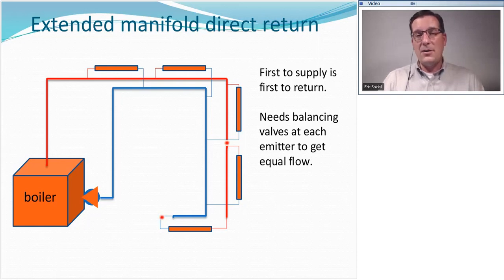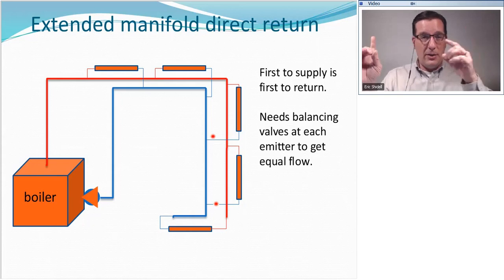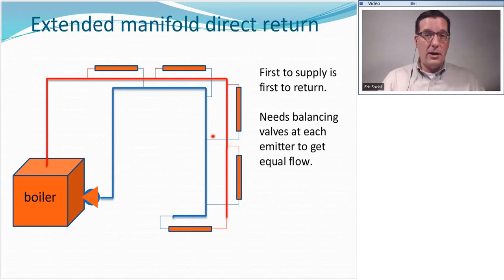But in order to make this work, we have to add the expense of putting balancing valves in each one of these branch lines to equal the flow through the whole system. And that will often be done or not done. Sometimes they're eliminated as a source of value engineering, and that leads to its own set of problems. And then you get another reason to stick your head up in the drop ceiling and observe what kind of system you have.